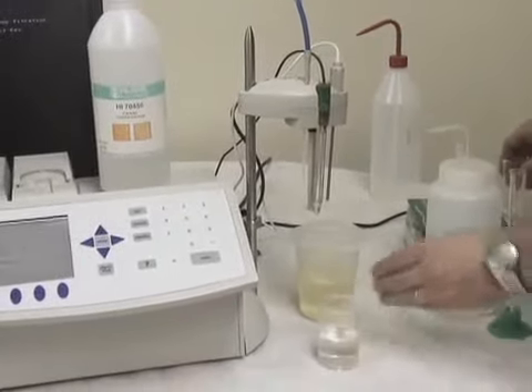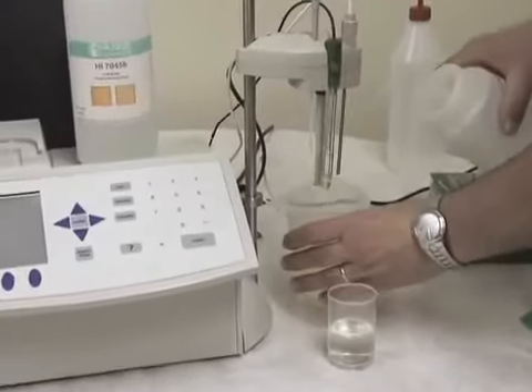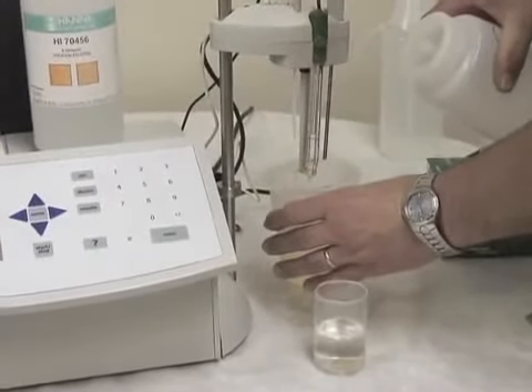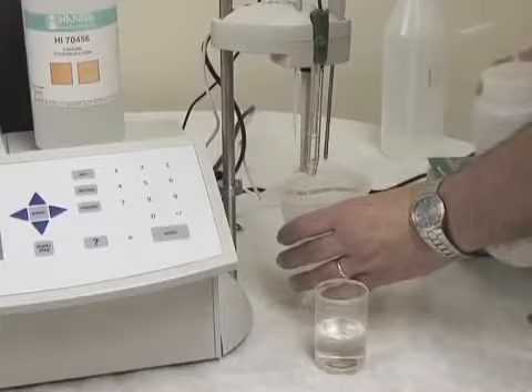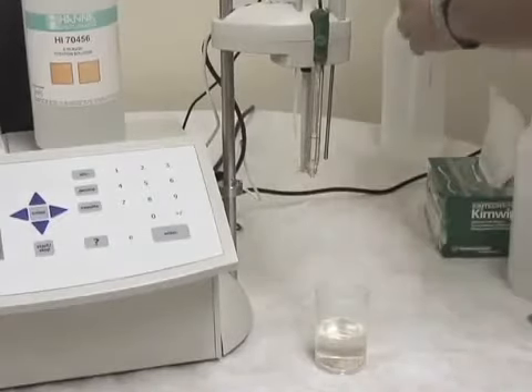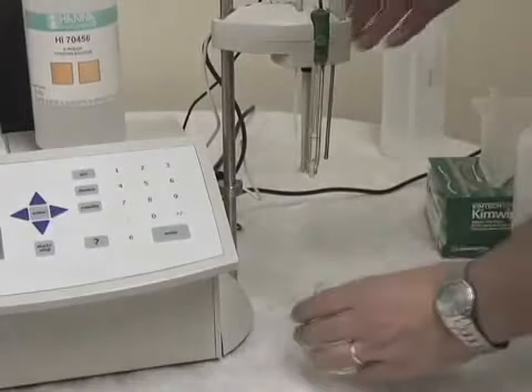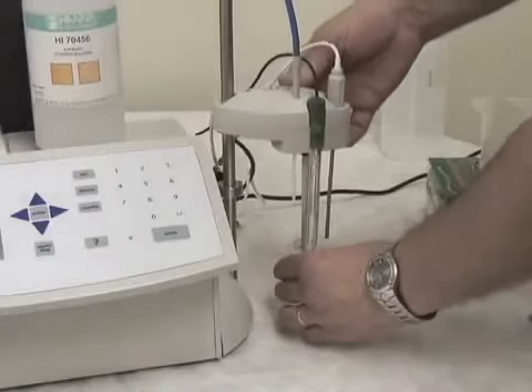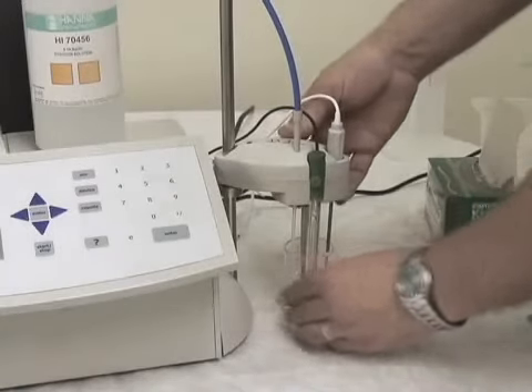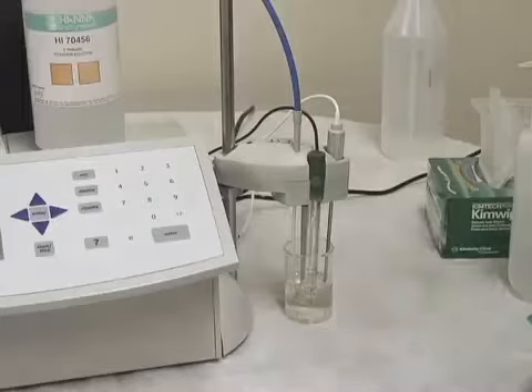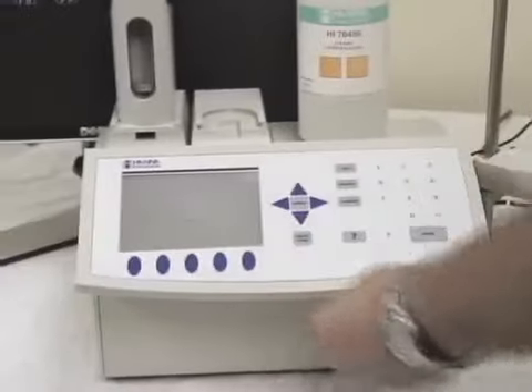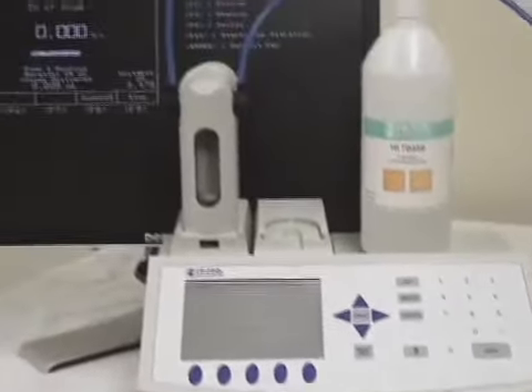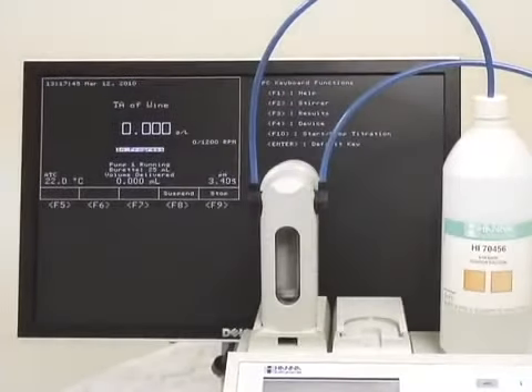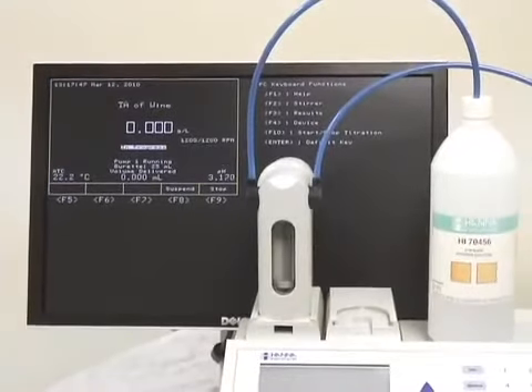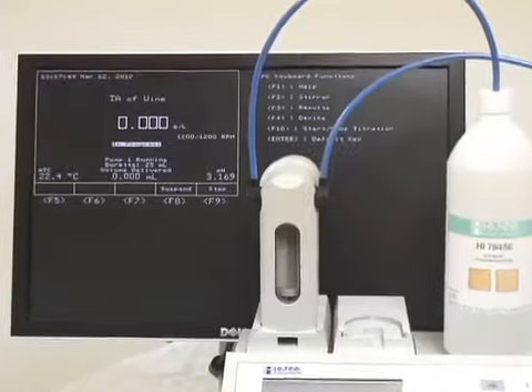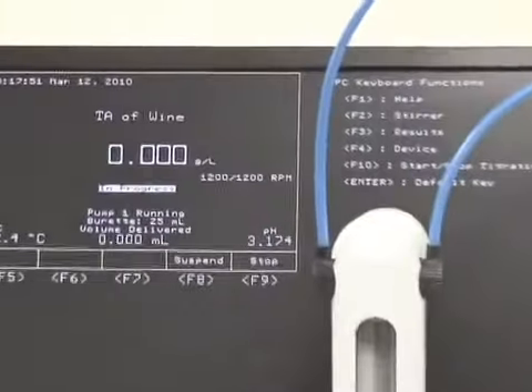Okay, so we have our sample. We're going to rinse our probe and stir. Since we're using deionized water, we do not need to dry it here. Okay, place your beaker under the stirrer and probe, lower it down in, make sure you're below your junction, and simply hit start. The 901 is going to mix for 10 to 15 seconds, whatever is programmed into the test at that moment, and then it's going to start its titration.